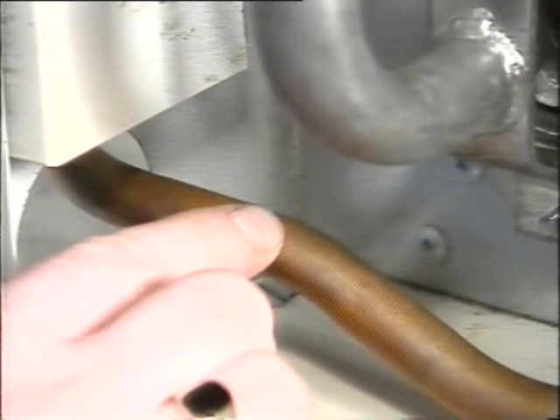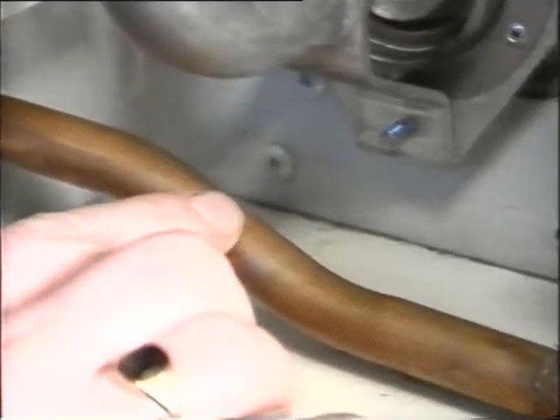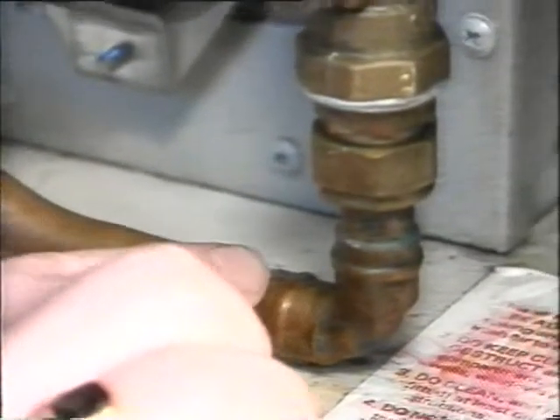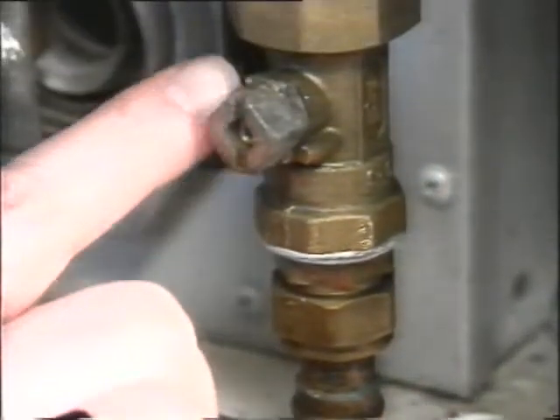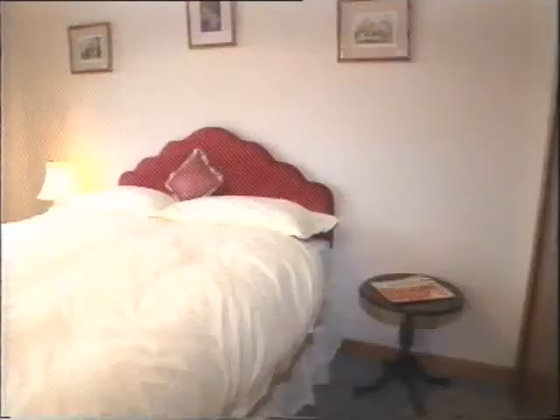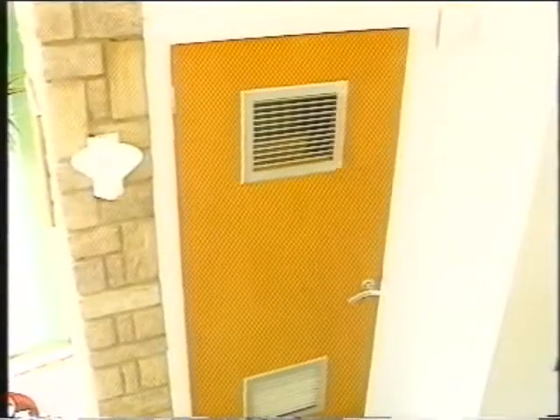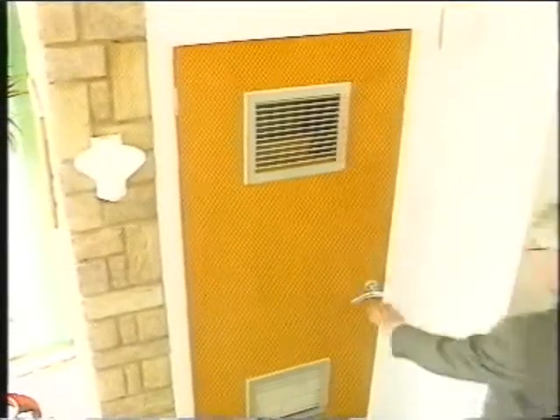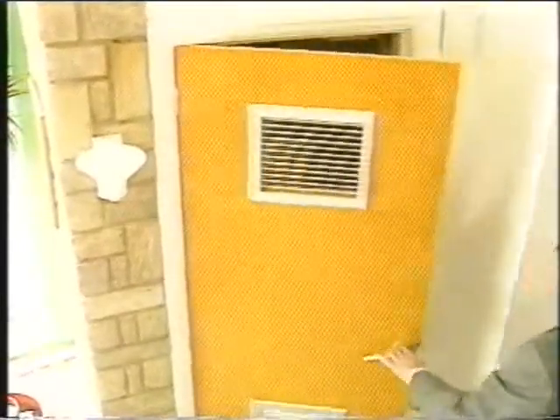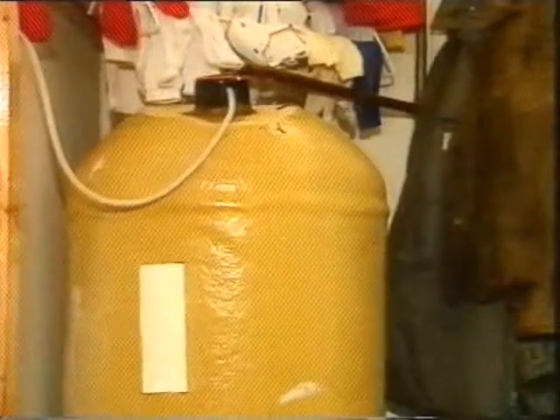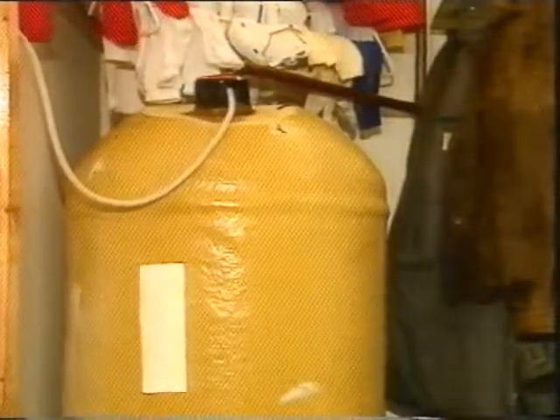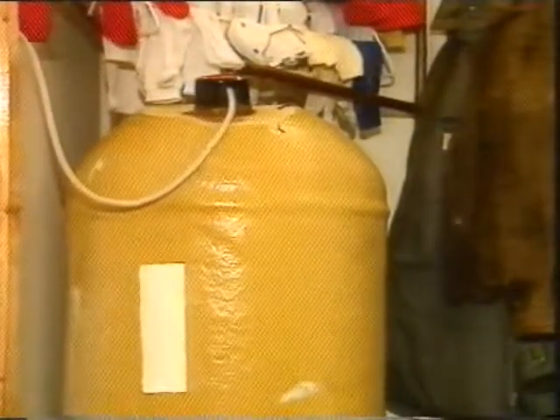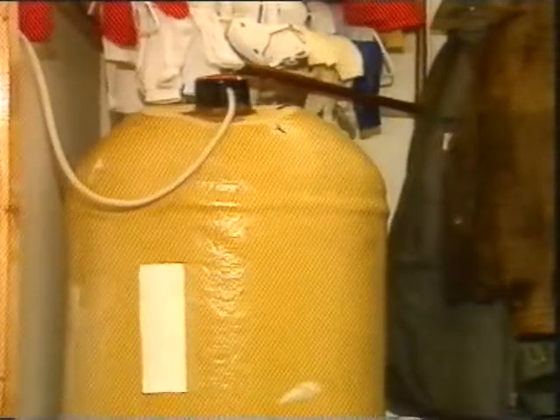Heat input rates are usually around 4.4 kilowatts, so the gas supply pipes should be 15 millimeters in diameter. They can't be installed in bathrooms, bedrooms or bed sits, and if they're fitted in an airing cupboard, the cupboard must have low and high level vents with at least 90.3 square centimeters of effective area. When you're satisfied with the installation, the appliance has to be commissioned before it can be used.